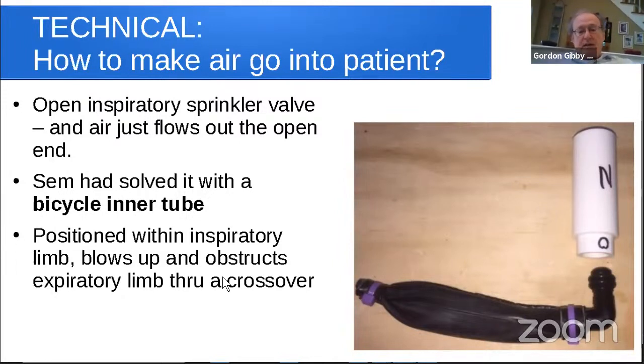So Sim had solved that by building a fancy but elegant valve with a bicycle inner tube. It was positioned so that a portion of it was exposed to the inspiratory limb, the limb that's supposed to go to the patient. That would see the air pressure and blow up, and it would obstruct the expiratory limb through a crossover portion. And that way air would go into the patient. When you close the sprinkler valve, this bicycle thing would automatically just deflate, and it would let the air come back out of the patient.